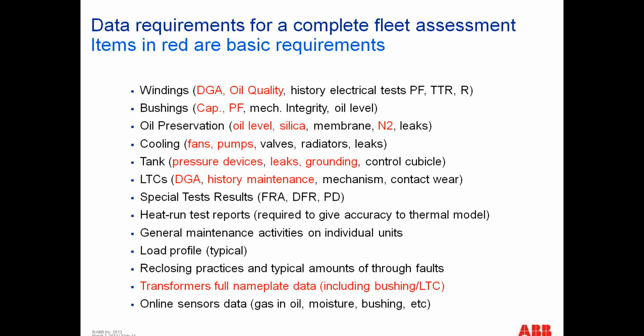You know, I mentioned bushings, oil preservation systems, cooling systems, LTCs. All of those things are important to look at. And what's really critical is that you understand the design of a specific transformer. It's just like any of the people on this call. We have different DNA. Truly, we're going to fail eventually in different ways. And transformers are the same way. The manufacturer produced maybe the issues and the understanding and the state of the art at that manufacturer at the time, all put limitations on how long that transformer is going to last.